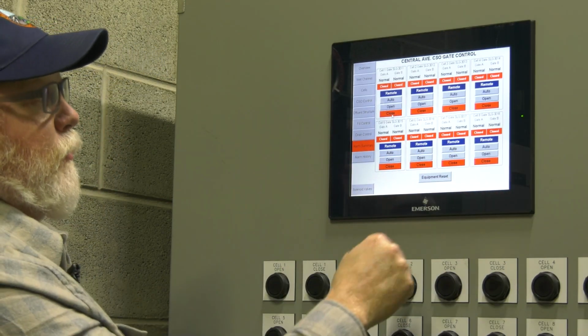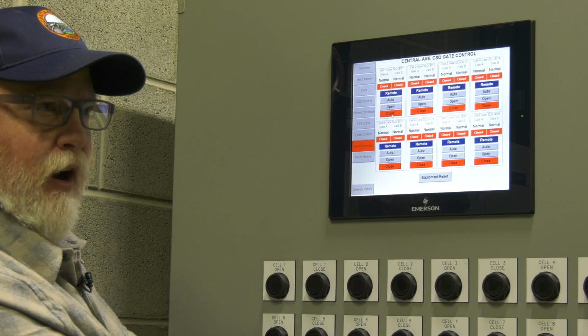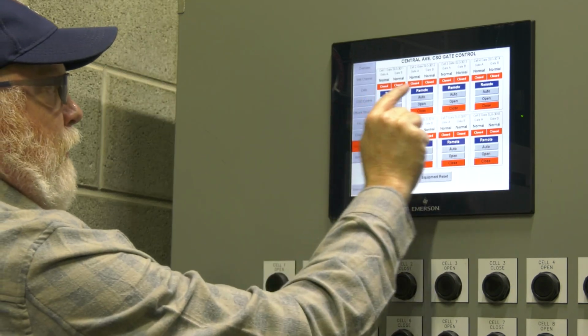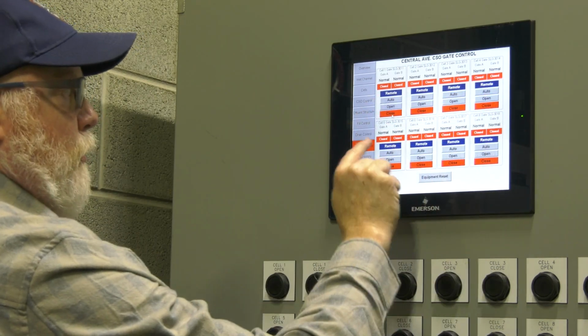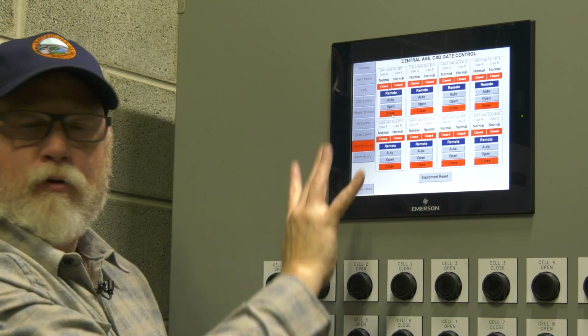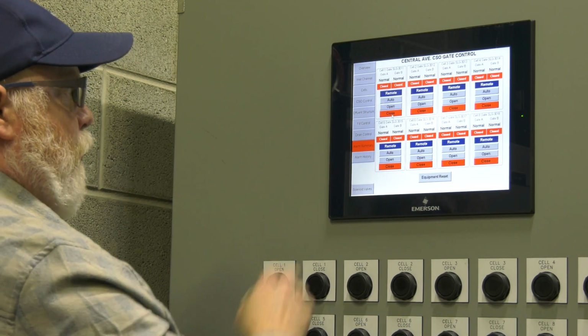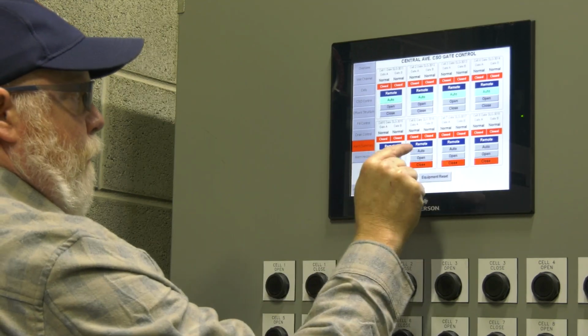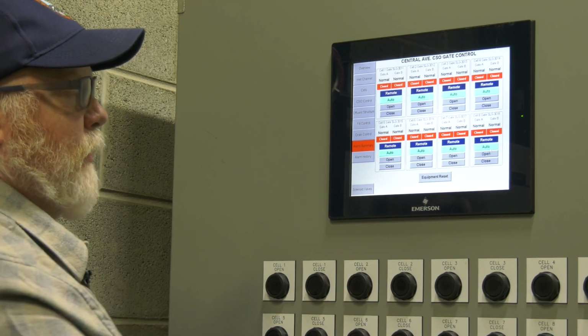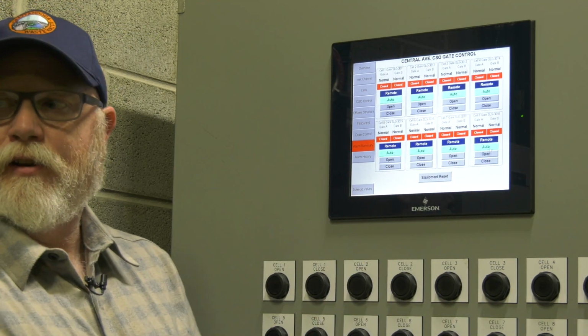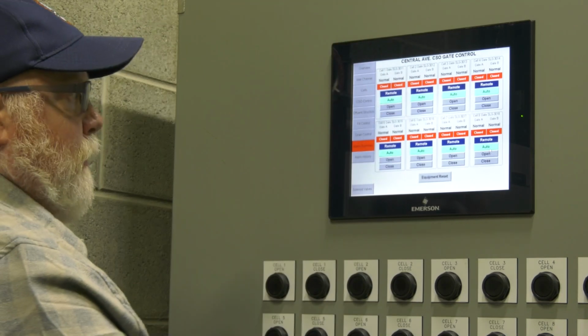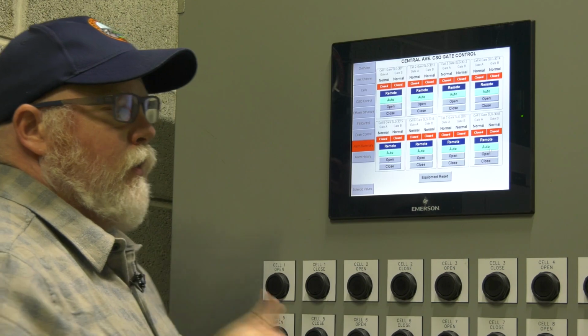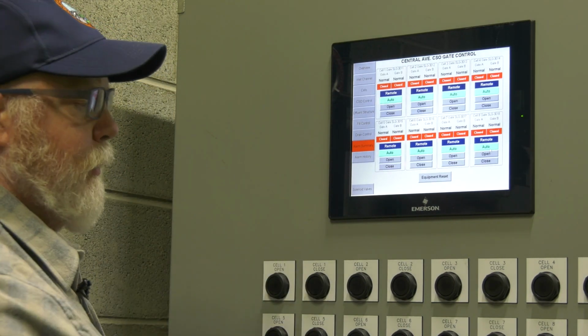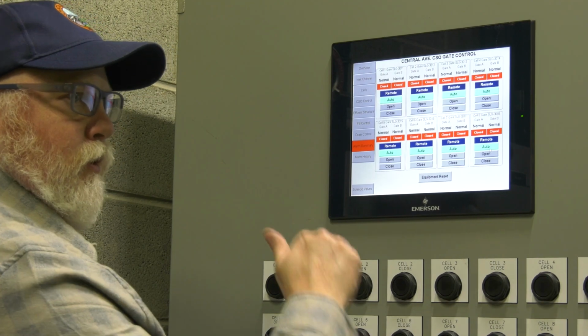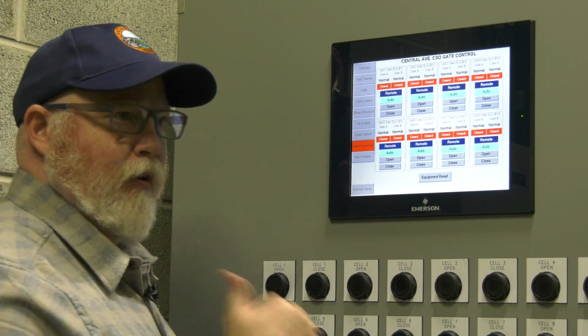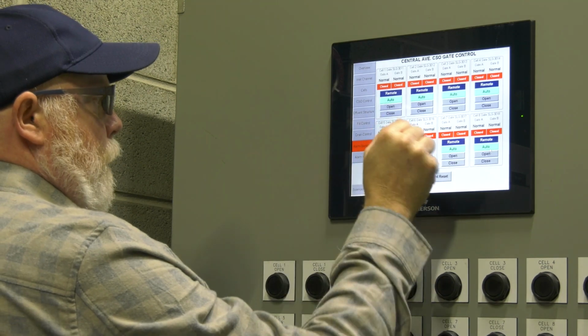This is actually remote manual control. If you leave this in auto, and you leave all of these here in remote, then this is just manual control from the screen. There's no automatic control of the gates. Now, if you put it in auto, then you're in auto control, and the CSO will function based on the control strategy. If you're at the other site, remote IO1, and you want to open and close gates from out there, I don't know if you'd ever do that, then you leave this in auto and you'd have control out there. If you leave this in manual, you're going to have no control out there.